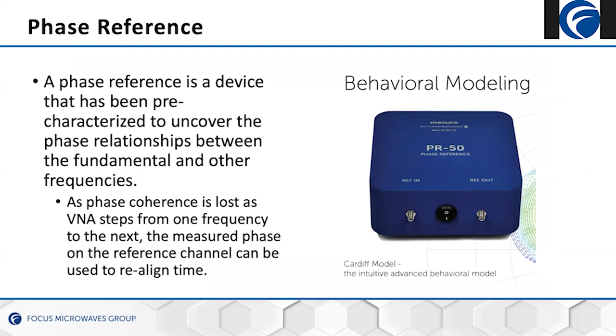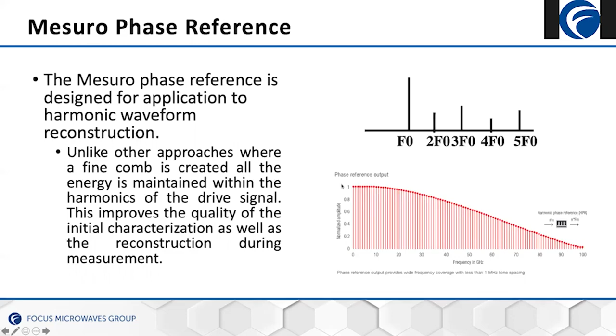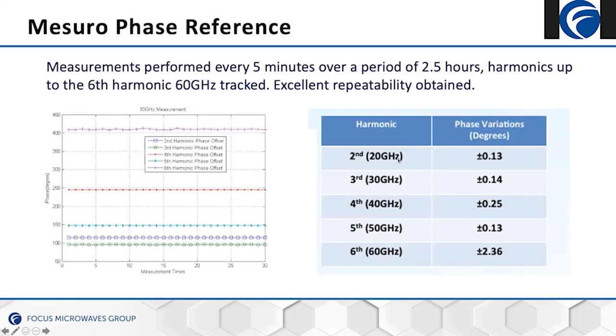For example, this is taken from Keysight's PNA-X data sheet, but it just gives you an example. We stimulate the device that's inside the phase reference and measure the response, and as you can see over time, here's an example of one, and this is the phase variation over multiple hours. So we do this long-time calibration and see what the variation in that phase is.